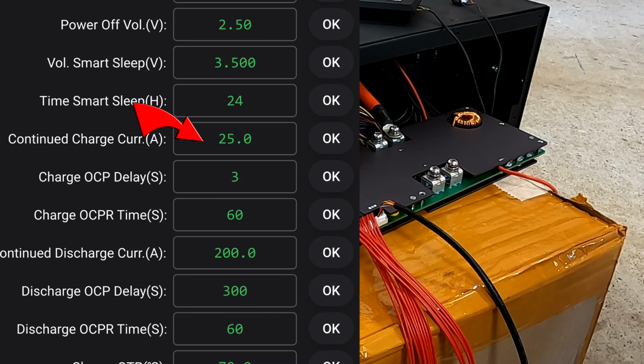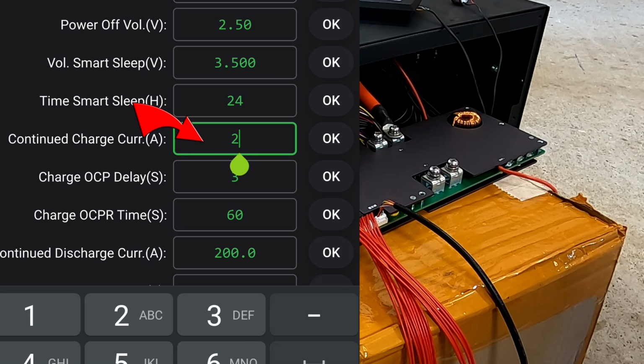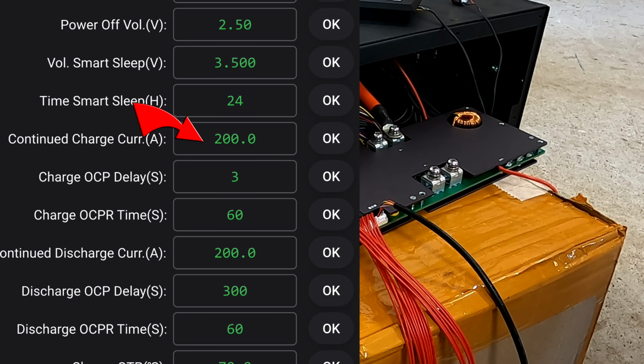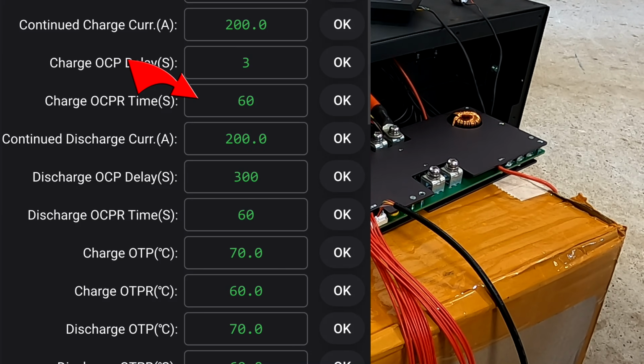The continued charge current sits at 25 amps. We can set this one here to 200 amps for our BMS and battery. The charge overcurrent protection delay sits at 3 seconds, that's fine. And we have a charge overcurrent protection recovery of 60 seconds. So that means if we would charge the battery with more than 200 amps for 3 seconds, it would disconnect your charger. And then it waits 60 seconds and then tries again. If it still measures 200 amps for 3 seconds, it keeps repeating this until the charge current is lowered below 200 amps.